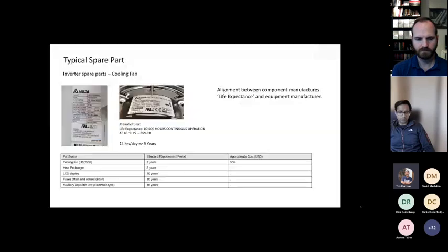So if I take a real life spare part — this is a cooling fan out of an inverter. The manufacturer's recommendation is that we replace these every 5 years. But the manufacturer doesn't actually make this particular spare part; it's made by another company called Delta. If I look on the Delta website, it says their life expectancy is 80,000 hours of continuous operation. Assuming that fan works 24 hours a day, which it won't, that still gives me a life of 9 years. So I'm replacing it actually 4 years before it needs to be replaced.